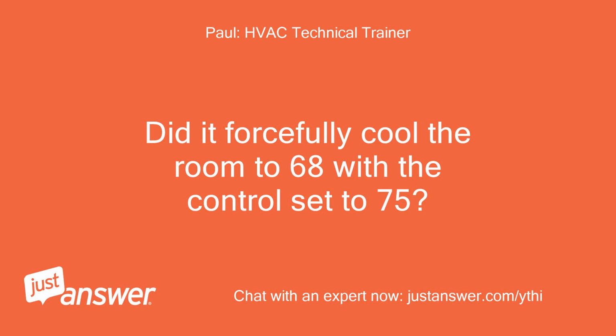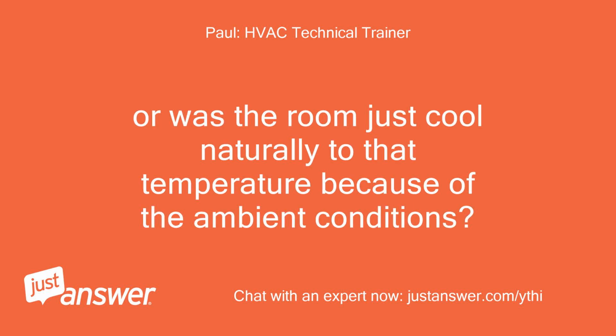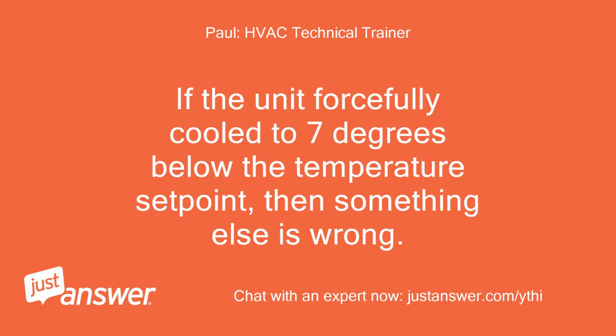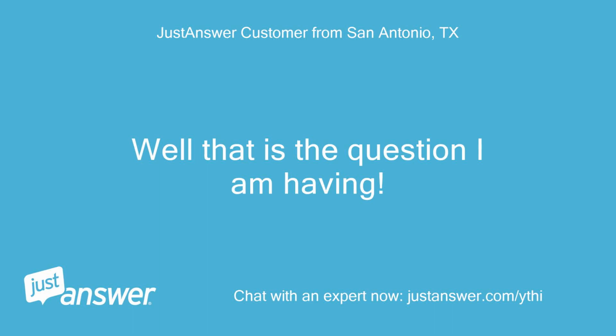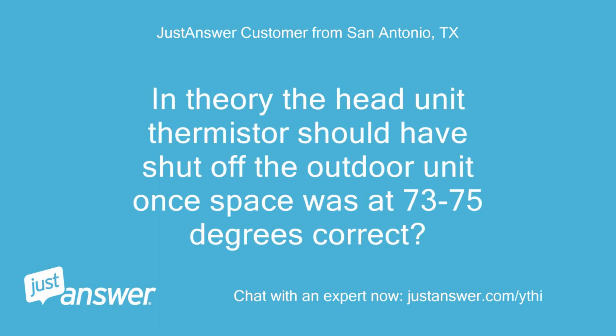Did it forcefully cool the room to 68 with the control set to 75? Or was the room just cool naturally to that temperature because of the ambient conditions? If the unit forcefully cooled to 7 degrees below the temperature set point, then something else is wrong. Well, that is the question I am having. In theory, the head unit thermistor should have shut off the outdoor unit once space was at 73 to 75 degrees, correct?